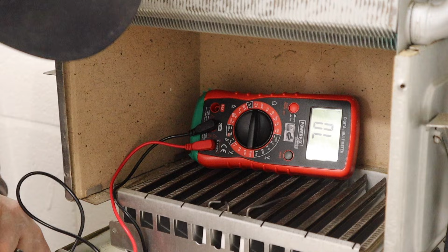Last thing I want to check electrically is the fan. So live off, neutral off. I've got this in buzzer mode to make sure we've got continuity. Hopefully we get a buzz. Yeah, and we've got a resistance, so hopefully that's working. It's free as a bird. A lot of these have a lot of problems. There's a little sensor on the top here, they have a lot of problems with them, but we'll see how it's going to go. But we've got two fans. Everything else so far we can check once we get power onto it and we get water onto it.